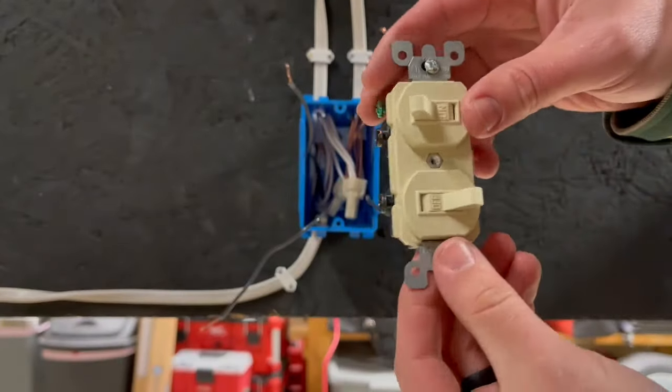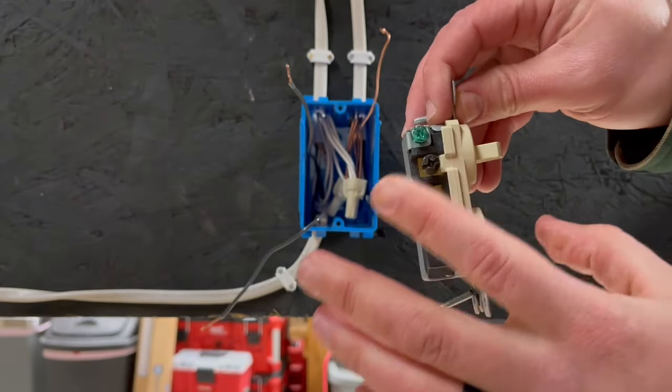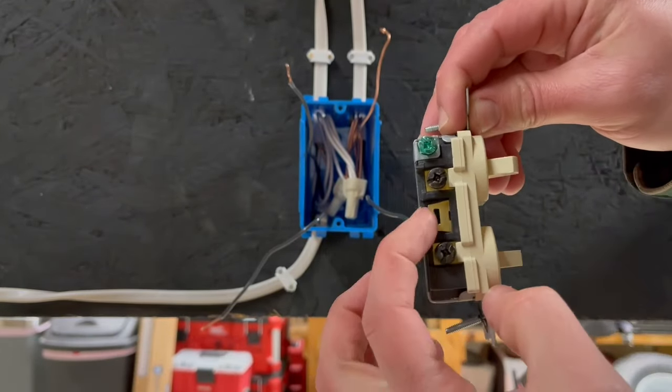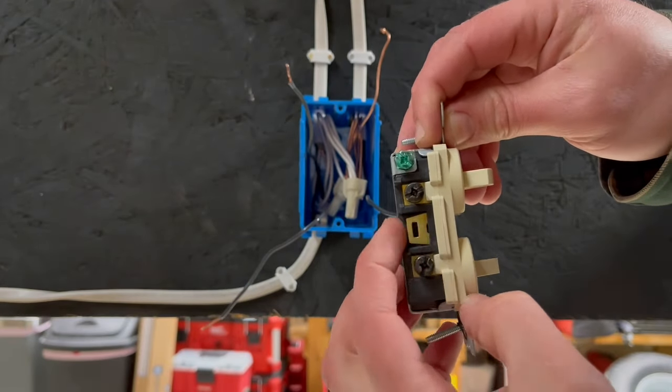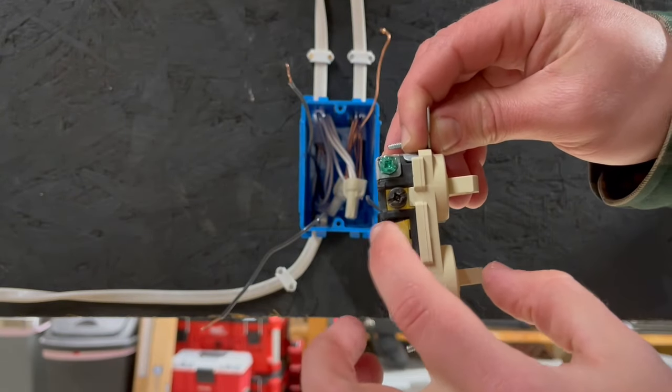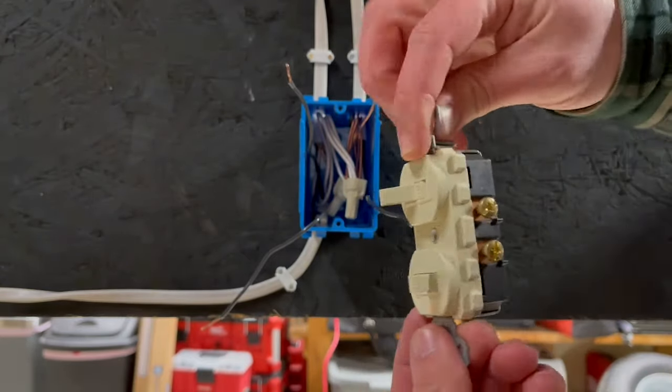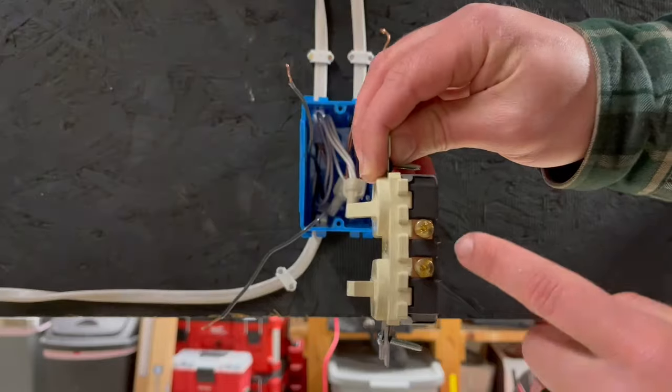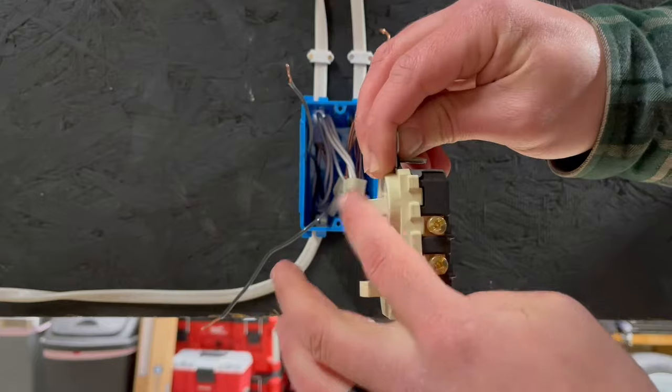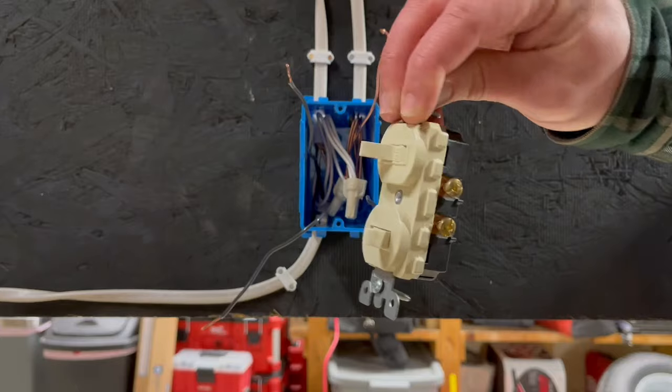Now closer look with this switch here. Our hots, our one hot is going to be on this black. It could be on either one because it is connected with this tab here. If you break this tab, then only one side of this switch is going to have power. So keep that tab on there. There's our ground, green for ground, our hot, and then here's where your two switch legs will go. So our light switch leg will go on this one so it's ran off this switch, and then our fan switch leg will go off this one so it's ran off this switch. Let's go ahead and put this in.